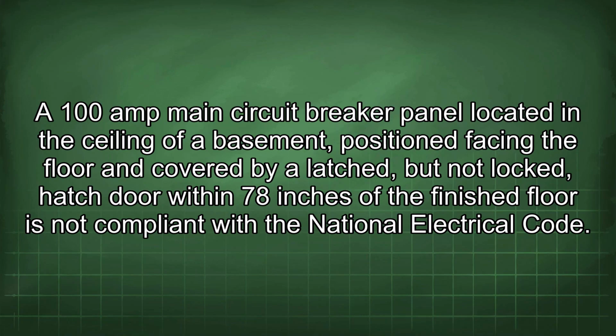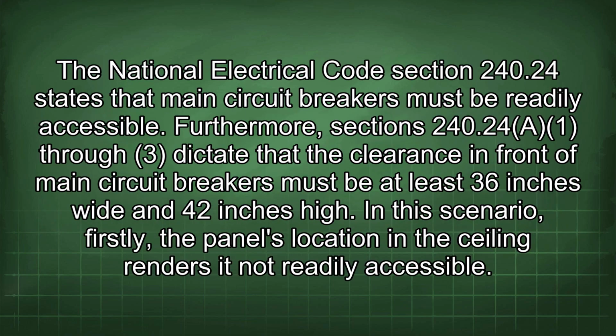A 100 amp main circuit breaker panel located in the ceiling of a basement, positioned facing the floor and covered by a latched, but not locked, hatch door within 78 inches of the finished floor, is not compliant with the National Electrical Code. The National Electrical Code Section 240.24 states that main circuit breakers must be readily accessible. Furthermore, Sections 240.24(A)(1) through (3) dictate that the clearance in front of main circuit breakers must be at least 36 inches wide and 42 inches high.